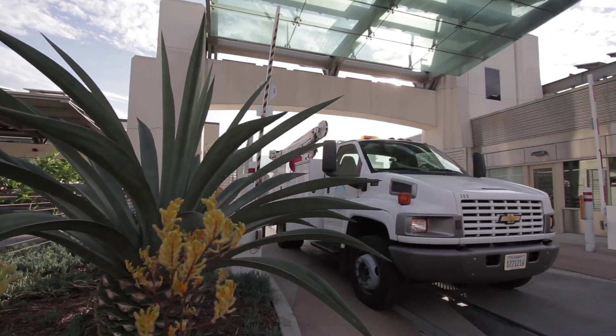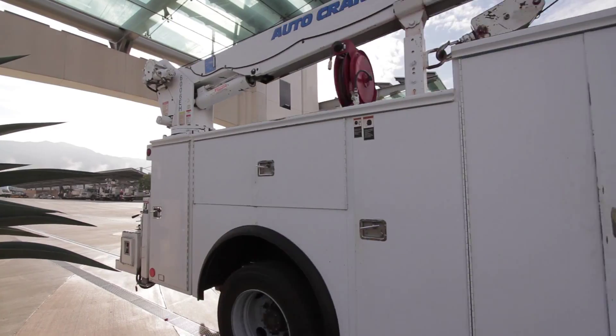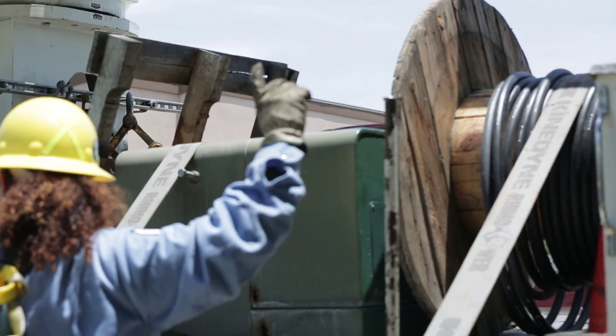In September of 2014, we had one of the worst heat waves seen in Burbank in decades — multiple days over 100 degrees and some pretty hot nights too. Because we were proactive and went out there and replaced all those transformers, during that major heat event the total number of outages due to transformer failures was zero. That's an impressive feat for a Southern California utility and something Burbank had never accomplished before. It's all thanks to using that data, monitoring our distribution system system-wide, and being able to look at all those distribution assets and take action.